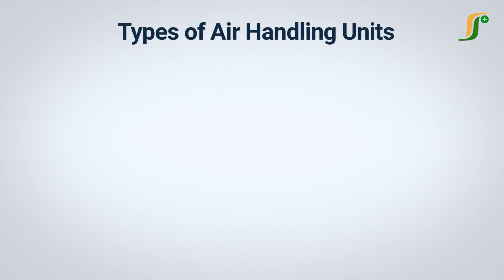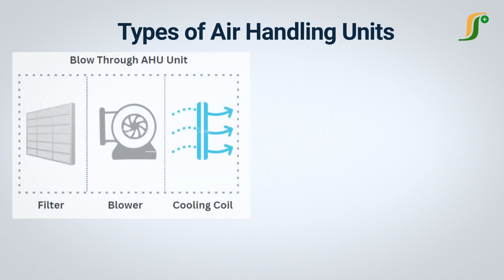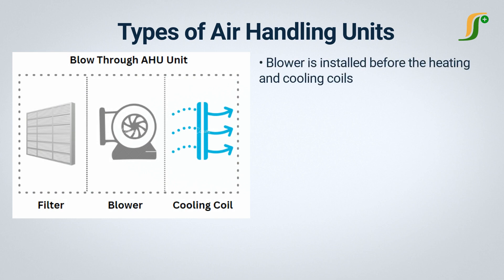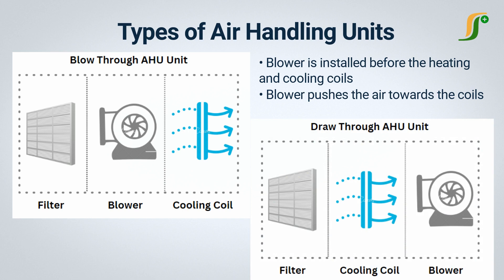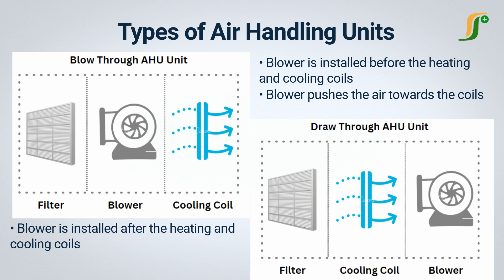Different types of air handling units are available. Each type has its own qualities and features. In a blow-through AHU, a blower is installed before the heating and cooling coils; the blower pushes the air towards the coils, and then air flows to the room through the ducts. In a draw-through AHU, the blower is installed after the heating and cooling coils, where it pulls air from the coils, increasing or decreasing air temperature as per the set temperature.